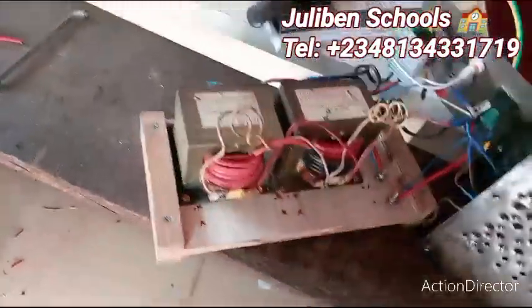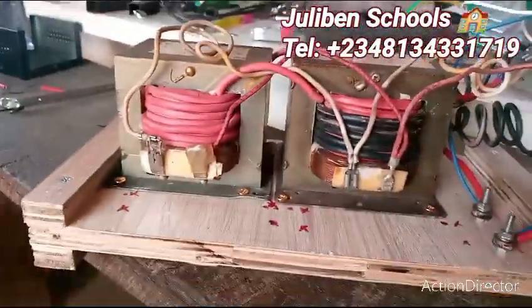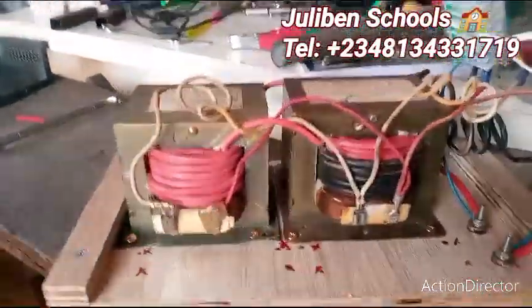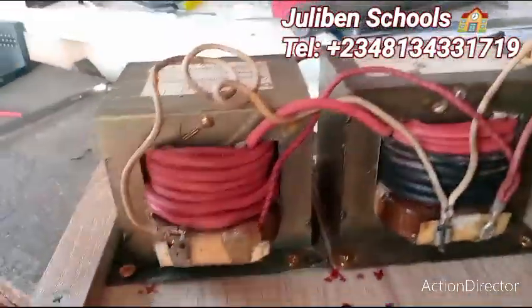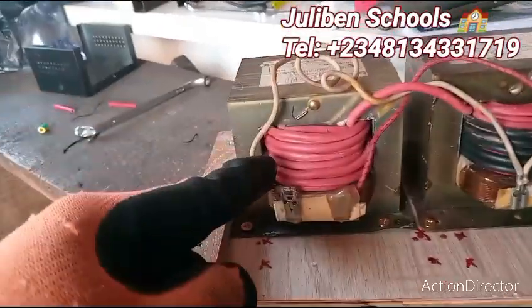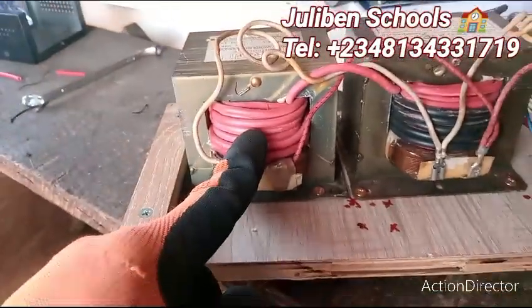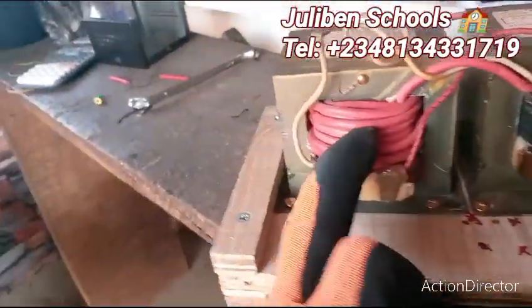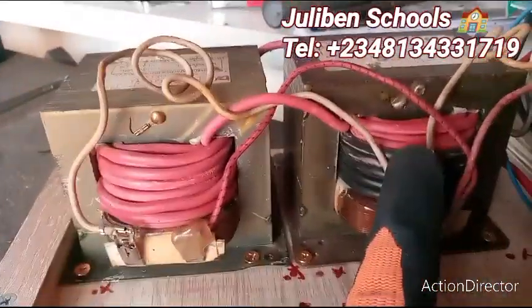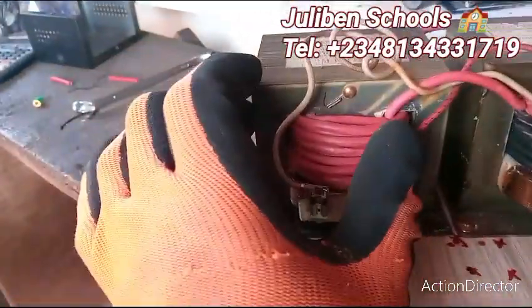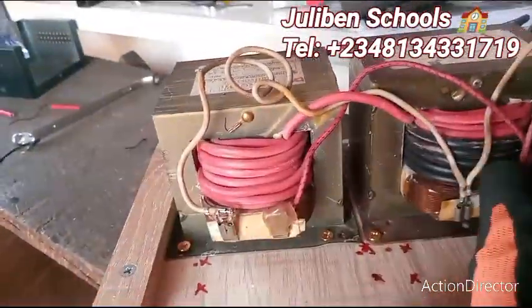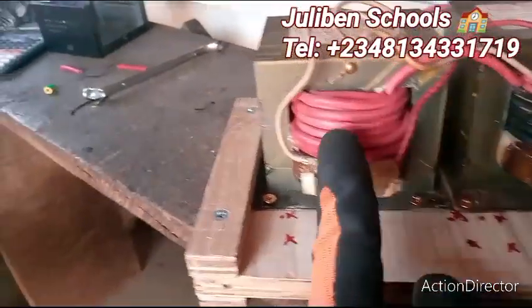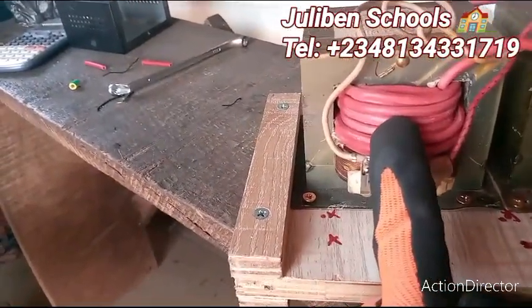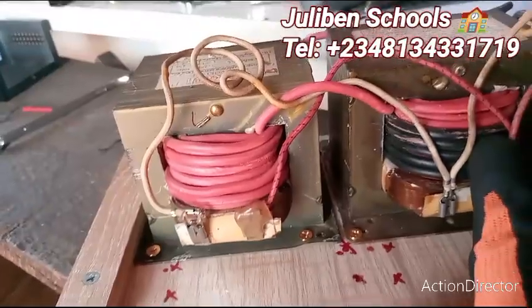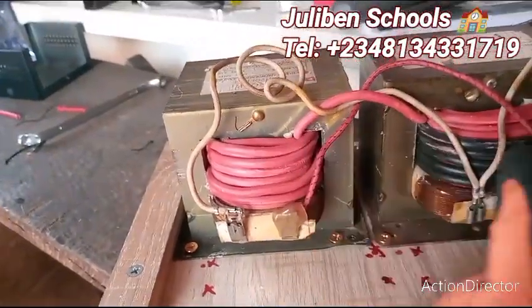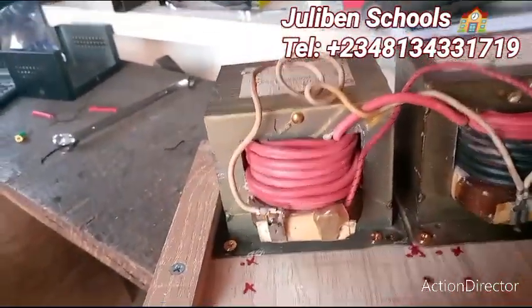Now, the number of turns you're going to use to achieve this secondary voltage is dependent on the number of volts you generate per turn. In this system, for example, the number of turns here is lesser than the number of turns here, and the reason is because this is a smaller transformer compared to this one in terms of the space provided for the secondary winding. We have a total of 17 turns here, while here we have a total of 23 turns. If you sum everything together, it's roughly 40 turns, okay?